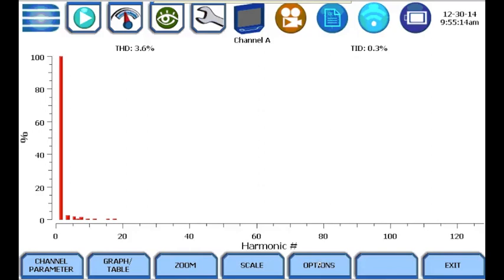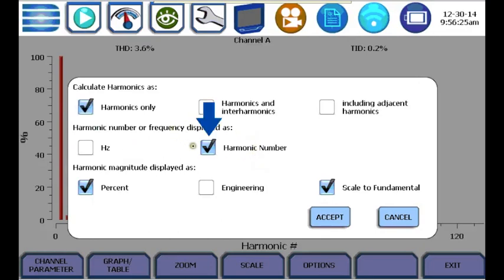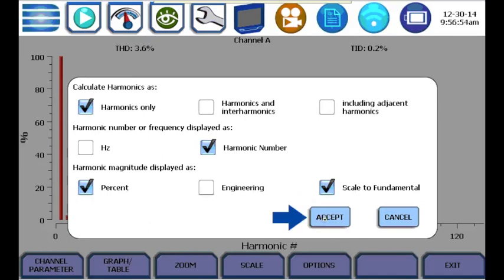To change how the harmonic graph is displayed, click the options button. In the harmonic options display, you can choose how the harmonics are calculated by using harmonics only, harmonics and interharmonics, and including the adjacent harmonics. You can also choose how harmonics are displayed, such as in frequency or by harmonic order number. The magnitude of each harmonic can be displayed as a percent, in engineering units such as volts, amps, or watts, or scaled to the fundamental. Once you've made your selections, simply press accept.